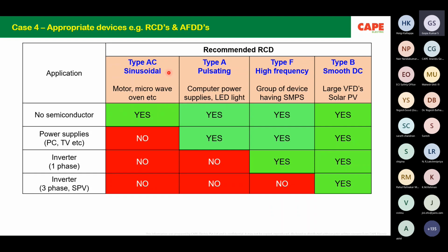Type AC is where you expect sinusoidal leakage. Type A, sinusoidal plus pulsating leakage. Type F, sinusoidal plus pulsating plus high frequency leakage. Type B is for smooth DC. These 4 RCDs are very categorically explained in the standard.